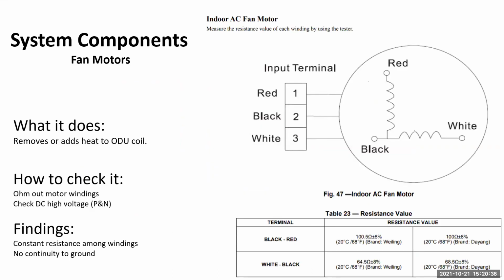So now we're talking about the fan motors, and these ohm out just like the compressor. They're 3-phase. They're going to check out like 3-phase DC motors. Once again, you look this stuff up in your service manual, and it'll walk you through it step by step. And temperature does have an effect on the resistance readings. If you have any resistance to ground, replace the motor. You obviously want to see if the motor spins freely, if it's broken. I've seen broken blades and things like that. They're just plastic. If a chunk of ice hits them or something, they could easily break.